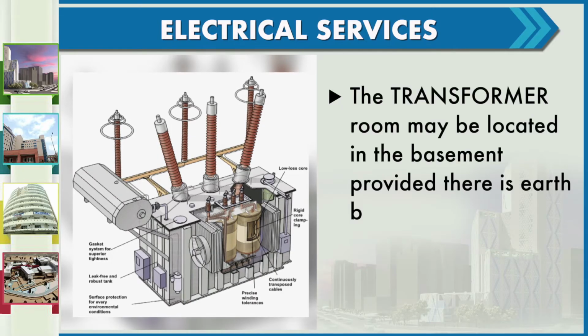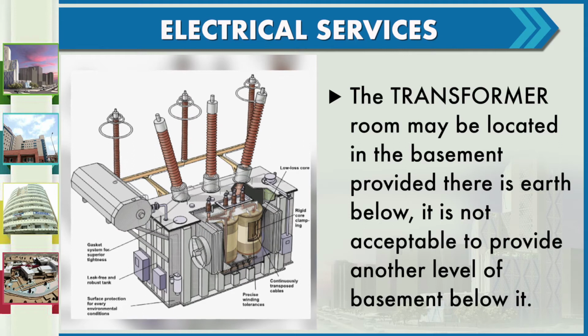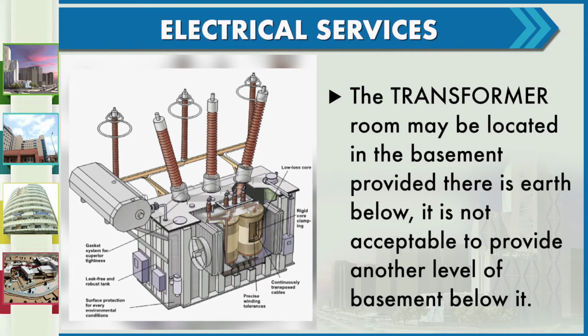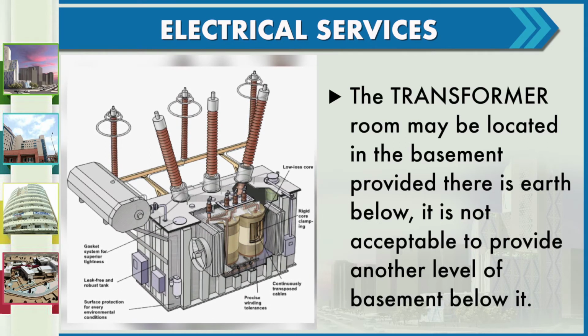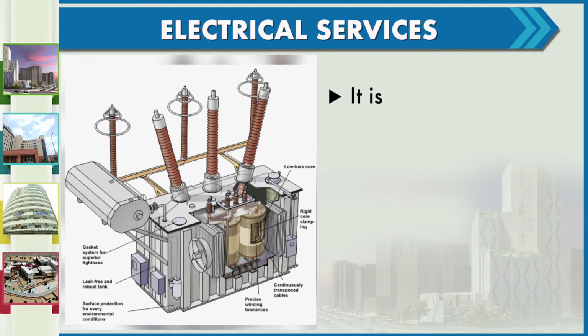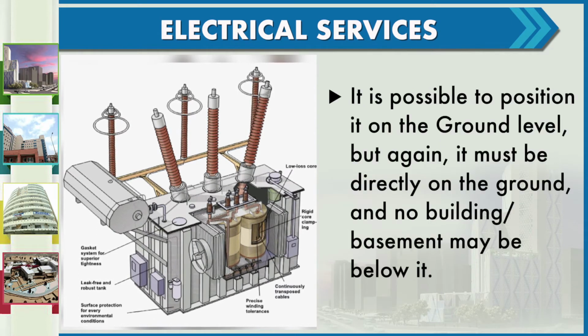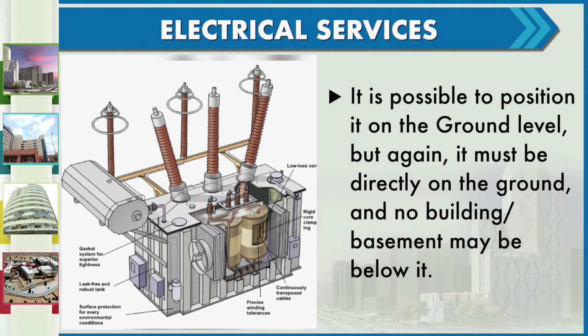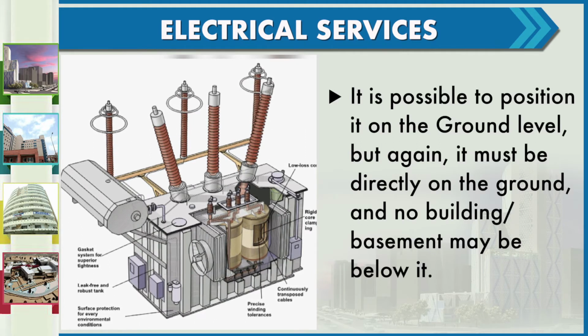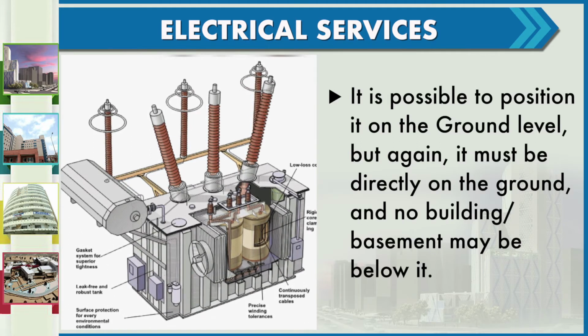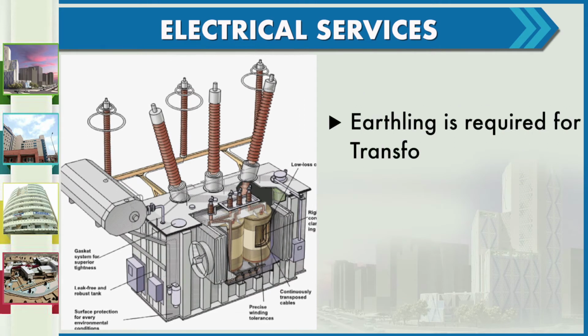The transformer room may be located in the basement provided there is earth below. It is not acceptable to provide another level of basement below it. It is possible to position it on the ground level, but again it must be directly on the ground and no building or basement may be below it. Earthing is required for the transformer room.